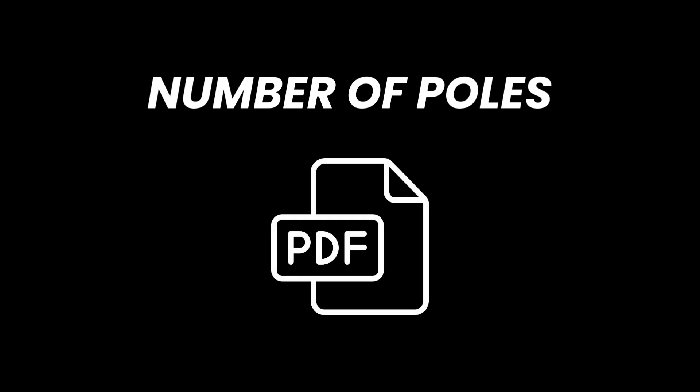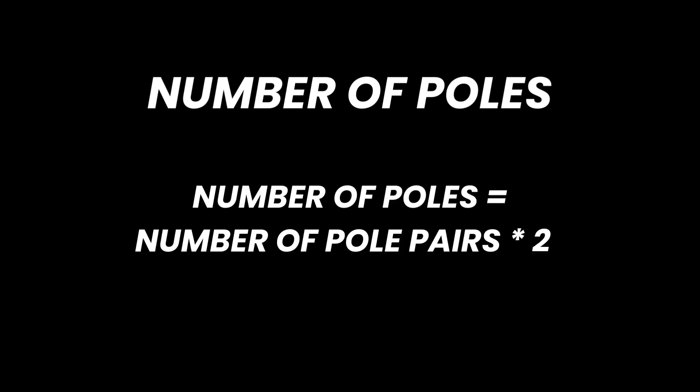Number of poles. The number of poles is crucial information for ensuring the motor controller's correct performance, which is why it is important to assign the correct value. It's possible to find the number of poles in the data sheets of the motor. If the data sheet provides the number of pole pairs, multiply it by two to obtain the correct number of poles.